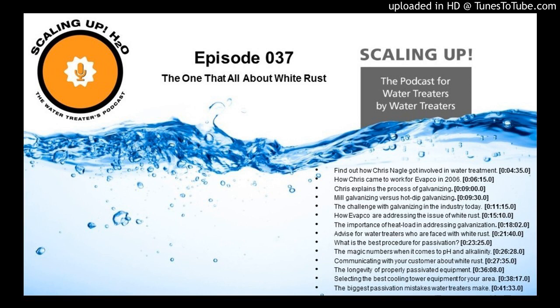Early on, when I would talk to water treatment guys about the problem, I'd always ask the same question: what's the most important parameter? I won't say 100% of the time, but the vast majority of the time, experienced water treatment guys would point to the pH or the alkalinity of the tower water or the spray water.